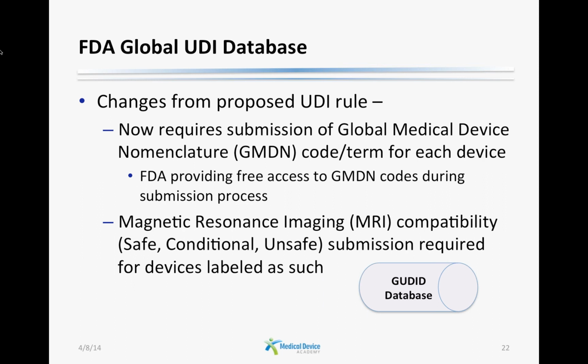Another change deals with MRI compatibility. If you make a claim for your device and have the test results to prove your claim of MRI compatibility, this information is now required as part of the submission to GUDID.